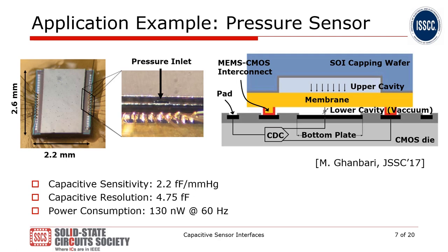This work targets intracranial pressure monitoring using a customized system. Due to the limited implantable space, the system thickness is limited to only hundreds of micrometers. This is resolved by the MEMS and CMOS co-integration approach. The deflection of the membrane upon pressure difference at the lower and upper cavity will induce a capacitance change, which is sensed by the CMOS chip below. The sensing accuracy in the order of plus or minus 2 mmHg is set by the AAMI standard.